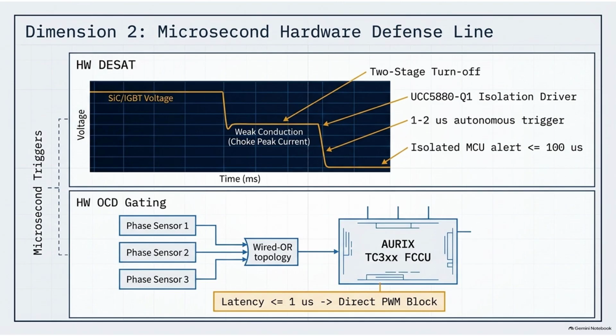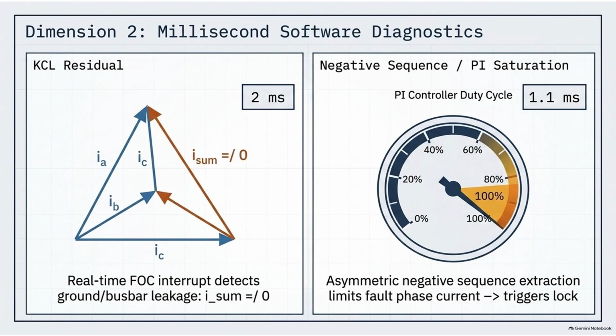It's amazing. But the gate driver isn't the only hardware reflex, right? There's also the hardware overcurrent detection, the OCD gating. Right. The primary current sensors have dedicated physical pins wired straight into the logic gates of the control board, completely bypassing the software loops. Wow. If the sensor detects a massive physical short, that analog signal propagates instantly and physically blocks the pulse width modulation, the PWM signals. In less than 1 microsecond, the specs say. Less than a microsecond, yes. Yeah. It essentially severs the nervous system of the motor.